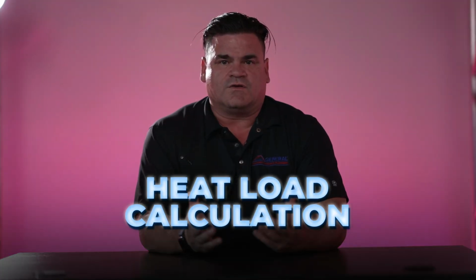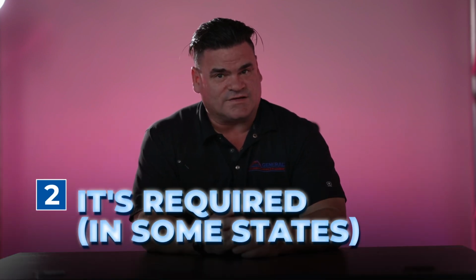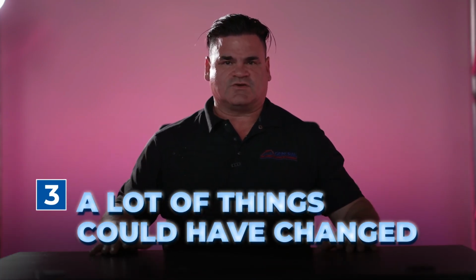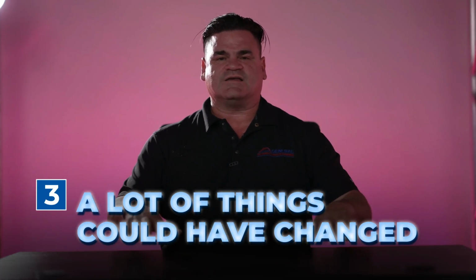Why do I need a heat load calculation if I'm installing a new HVAC system? Here's why. One, it's a best practice. Two, in the state of California and other states, it's required. Three, you're replacing your system, and a lot of things could have changed that would affect the size of the system.